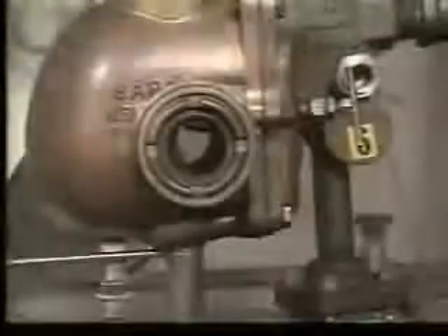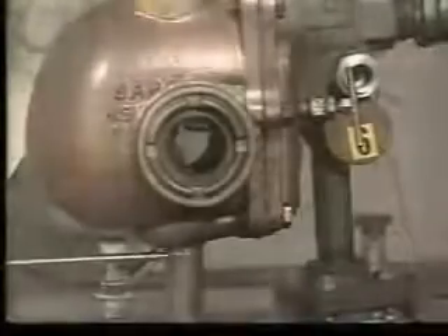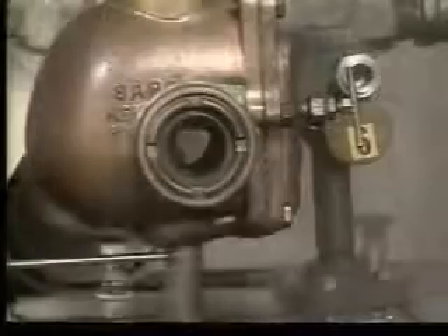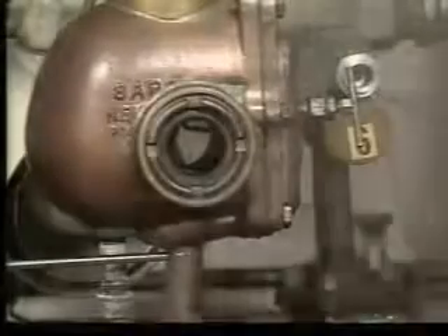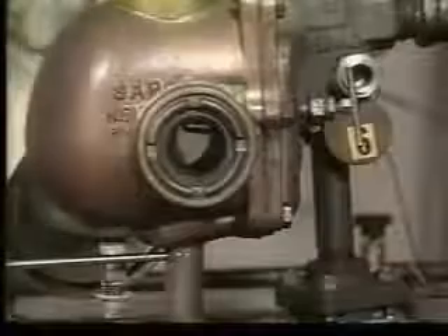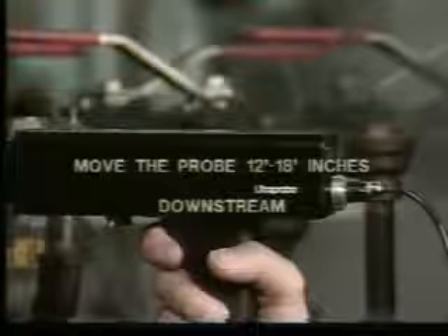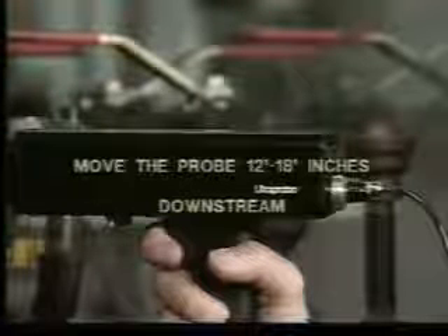A large rushing sound will indicate failure of the main valve or air vent. If recognizing these sounds is difficult, move the probe 12 to 18 inches and test again.